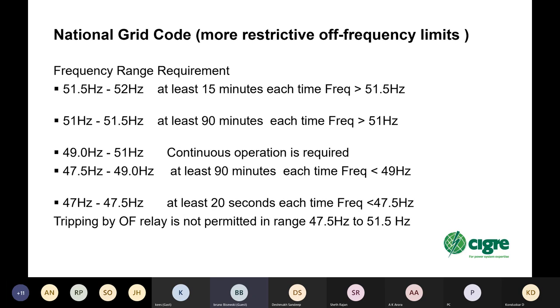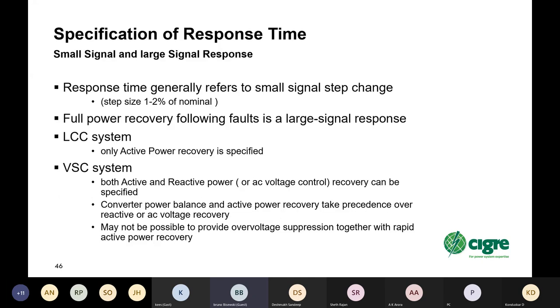And this is an example of a more restrictive off-frequency limit. And you can see that here, they've defined both the plus and minus range and said that if you're between 51.5 and 52, at least 15 minutes each time the frequency goes over 51.5 and so on and so on. So you need to specify what you want. It will affect the equipment design and will have some costs, but if you need it, by all means specify it.